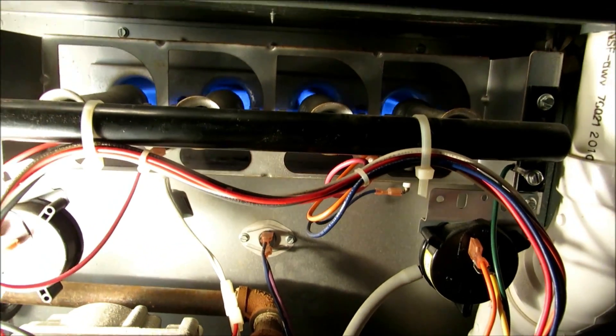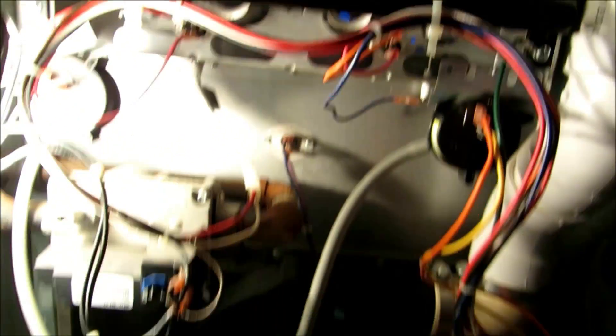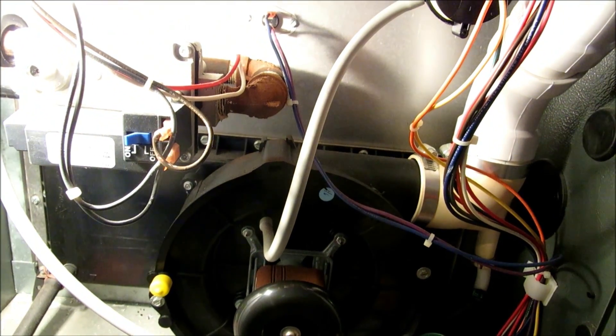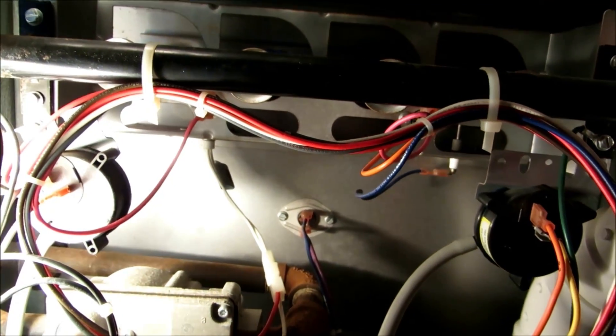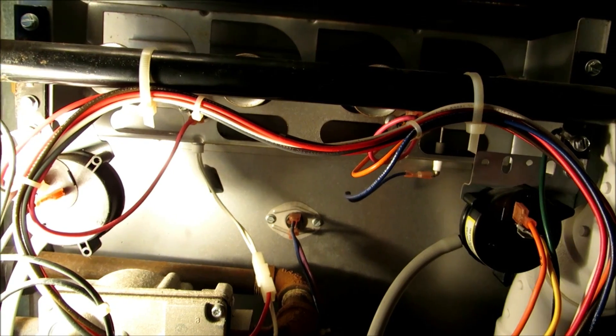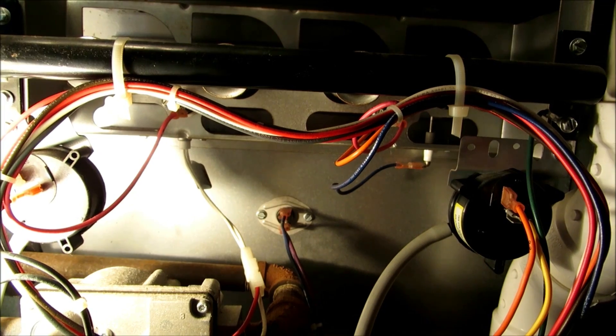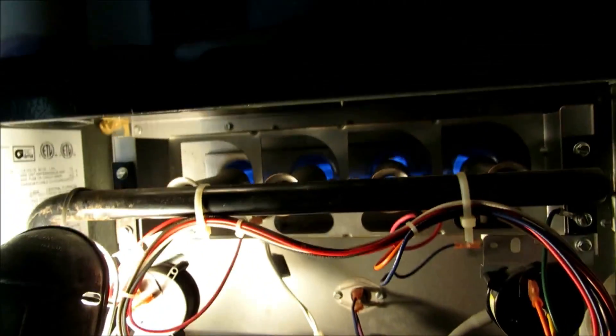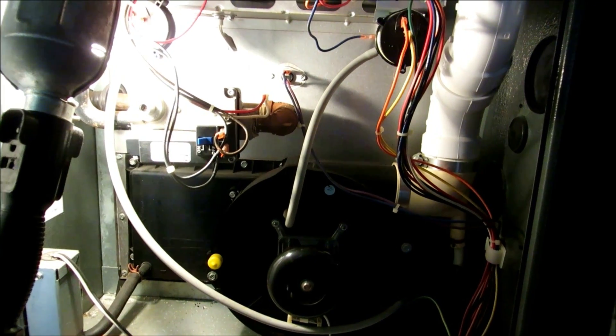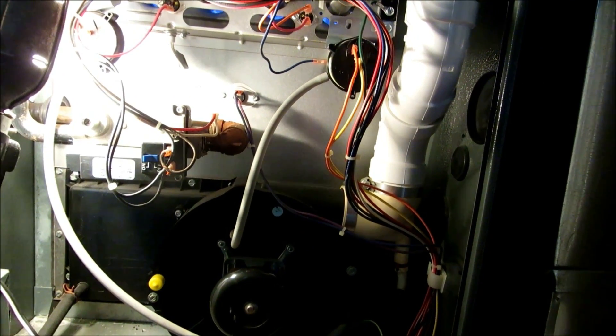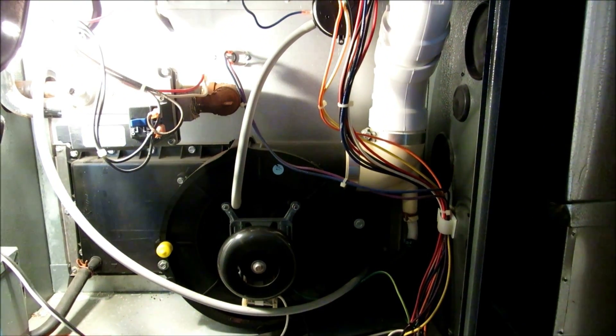All right. Within the next, I'm not positive about Goodman, but I'd say within 30 to 90 seconds, we're going to hear our blower motor, our bad blower motor that we just changed out, fire. This actually creates a little bit of heat in the heat exchanger. You don't want the blower firing up automatically or it's going to have a rush of cold air in your house. You want to have some heat in the heat exchanger. So we're waiting for our blower. And there we go, Brian. That's it, isn't it? That's it. Let's see if that vent feels a little bit better now. I bet it feels a little better now.